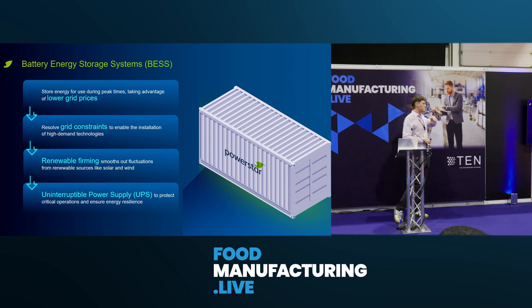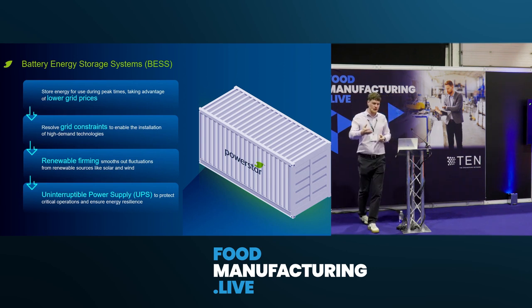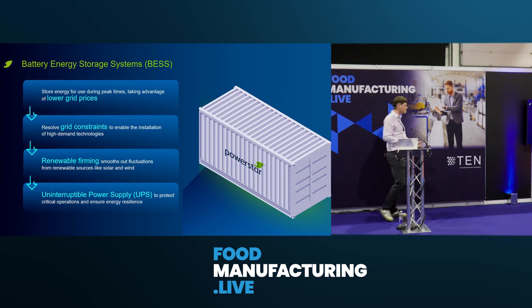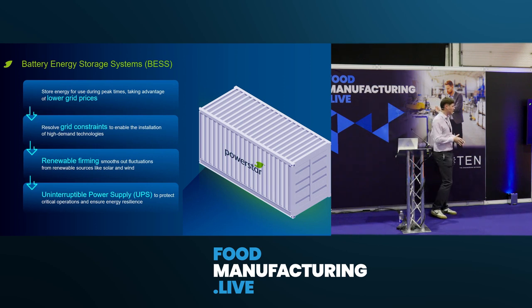We can back up the entire site load within 20 milliseconds. So we have a switching device that takes up the site load in an event, whether that's a grid outage, a frequency response issue, or a power quality issue. The UPS system ensures that within 20 milliseconds, the device switches over to load onto the BESS.